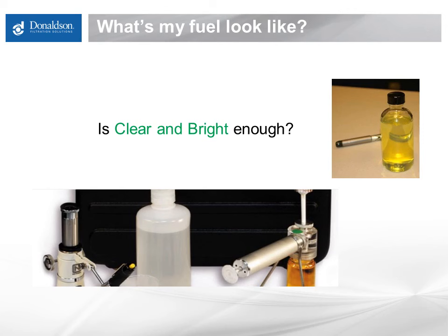These methods do not directly correlate or evaluate a fuel for its impact on equipment operation. The fuel user wants to ensure that the fuel will not create unexpected downtime when burned in their engines. Filterability is the property of fuel that allows it to run through a standard fuel system, including bulk filters or onboard filtration, and meet the expected design service intervals for fuel cleanliness levels. For the actual fuel user, directly assessing the fuel's tendency to plug filters is a more meaningful way to evaluate fuel and its impact on equipment and fuel system filtration.